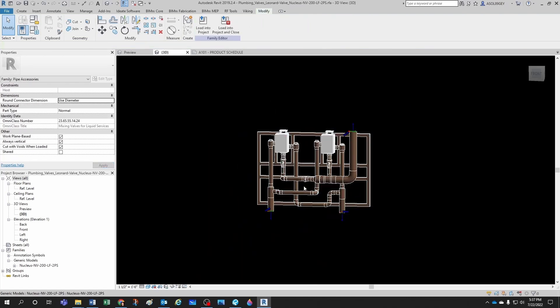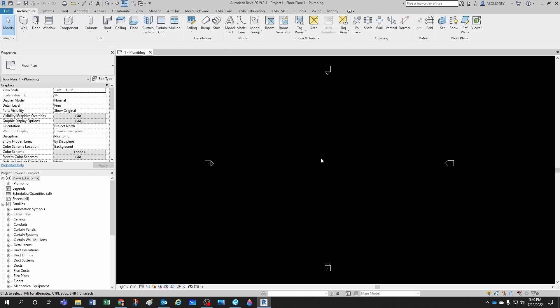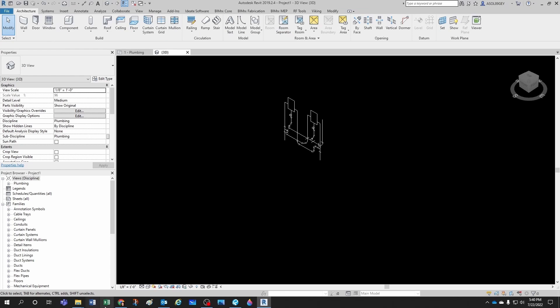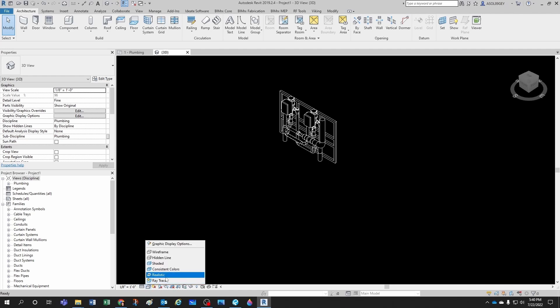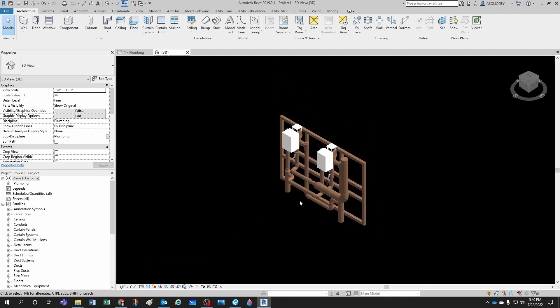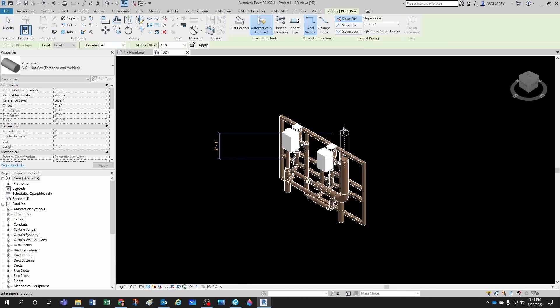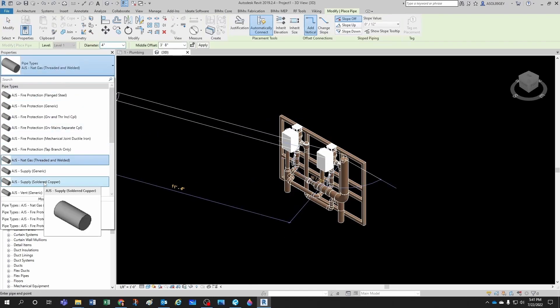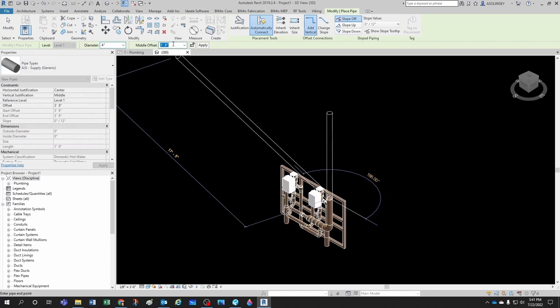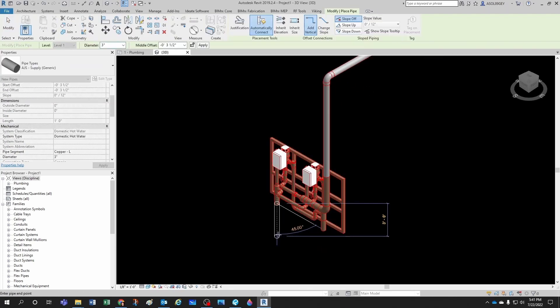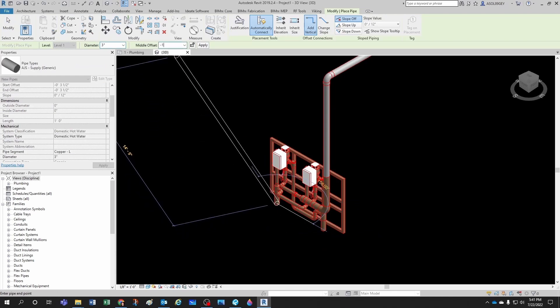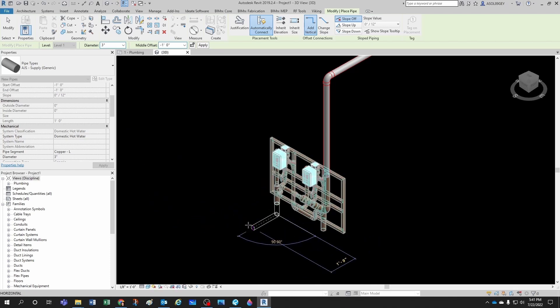I open a new Revit project and drop the mixing valve family in, placing it on a work plane. I switch to a 3D view and set the display to Shaded. Then I start drawing pipes — I draw a domestic hot water pipe at 10 feet of elevation, bring another pipe down to about minus one foot, and draw the cold water pipe similarly, also brought down to minus one foot.